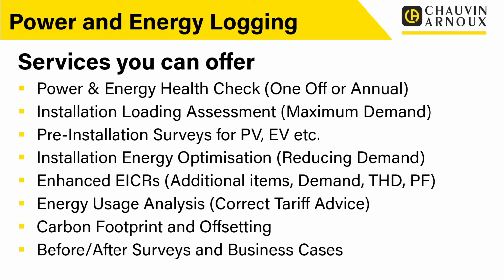On bigger installations you've got G59, with protection relays and so on set up to operate within certain parameters. You want to know the supply will be within those parameters before you install a whole solar farm, connect it all up, and then find it's actually out of spec when you try to connect to the mains. Then you've got to start speaking to the DNO about changing the transformer, changing tappings, increasing the size of supply cables, and all those issues you don't want to get into. That could mean the return on investment for the PV installation isn't viable anymore, because of how much work is required to get it into a usable condition.